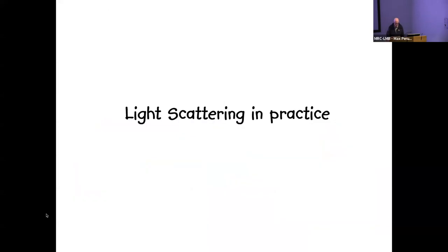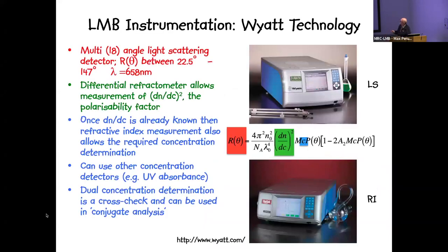How do we measure light scattering in practice for these applications? The instrumentation we have at the LMB is from Wyatt Technology Corporation. We have a number of these systems — one in the cold room and one in the lab at room temperature. They comprise different detectors: multi-angle light scattering measuring scattered light intensity over angle ranges between 20 and 150 degrees at 658 nm, and a differential refractometer to measure the refractive index increment as a function of concentration, giving the polarizability factor.